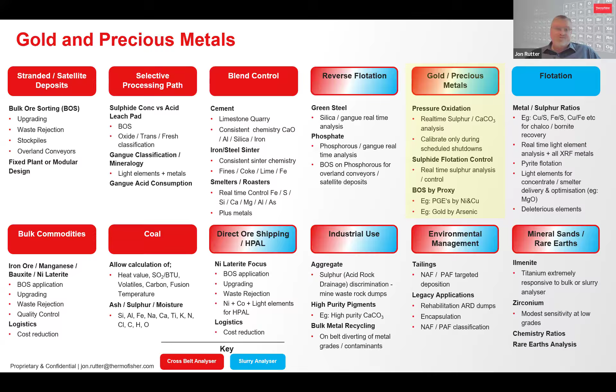But I suppose a few takeaways I'd like people to remember is what actionable task could be undertaken if you have the data to process less waste and recover more metal. It may be as simple as better quality product control or improved efficiencies, but don't fix what isn't broken. XRF is an excellent tool, but it does tap out at calcium when you get down to the light elements. So if you want actionable data for light elements that XRF can't deliver, either as a coarse product on the conveyor belt or as a ground slurry in process plant and tailings, then maybe PGNAA is for you.